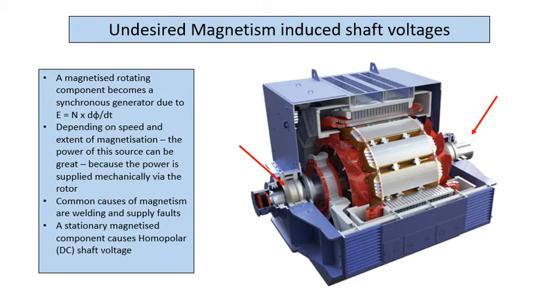You can also magnetize the bearing housing, and that's where you get a homopolar shaft voltage. And that's DC. Another reason is faults. If you have had a fault on a machine, and you've had massive currents flowing through it. I had a case where another repair company that does DC machines did a machine, and they connected all the DC field poles in the same direction instead of north-south, north-south. And afterwards they found that the shaft was magnetized. The reason is you had all these poles pushing flux into the armature, and it had to come out somewhere.